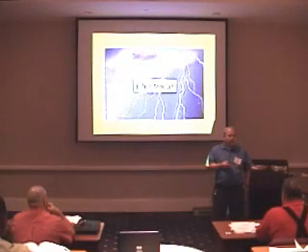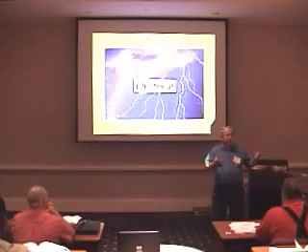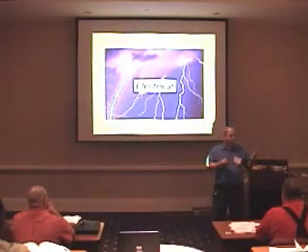When you start talking about dealing with electricity and high voltage, the people that actually work on that, work on it in some cases barehanded, but they're at the same potential. In other words, they are working at the same potential that wire is. In order for anything to seriously happen to them, what has to happen? They have to touch either the neutral wire or the ground, or another wire of different potential. That's like the birds on the wire. They sit up there, and as long as they don't make contact with each other, they're fine.